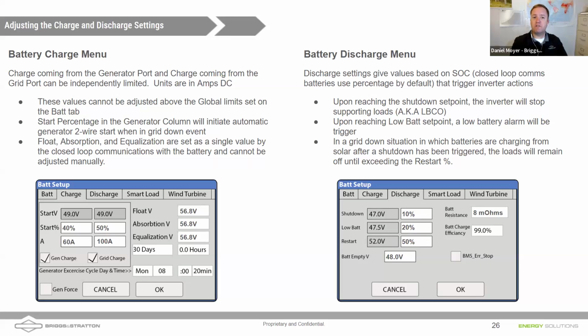Nathan, I had a question. So you mentioned that the float, absorb, equalize are automatically populated by the battery BMS. I've heard that sometimes it's good practice to not connect to the battery comms, program those settings to the default, and then if ever closed loop comms are lost in the future, the Sol-Ark would default back to some of those settings appropriate for the battery. Is that a good idea?